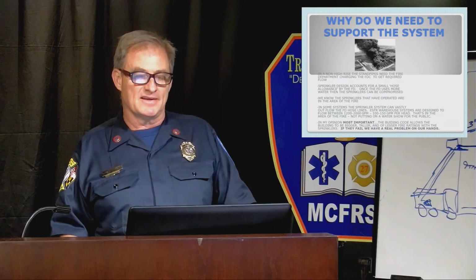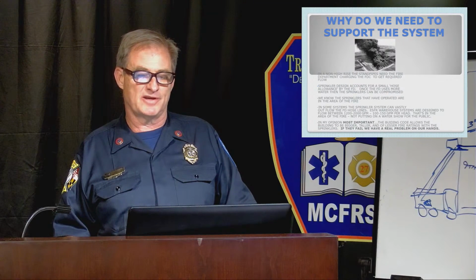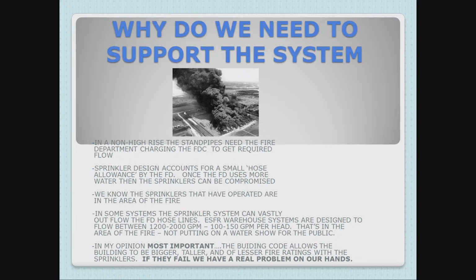I don't know if anybody recognizes the picture on the screen. Let's go back to the screen. So that is the Kmart warehouse fire. That is a fully sprinklered building. Now, the details of it were that aerosol cans were exploding and basically shooting across the warehouse and past fire doors. But this is a fully sprinklered building, and this was a total loss. At the time, it was the highest dollar loss by value in the United States, and I think this was '79, '80, '81, something like that. Fully sprinklered building, and there you go. It's off to the races.